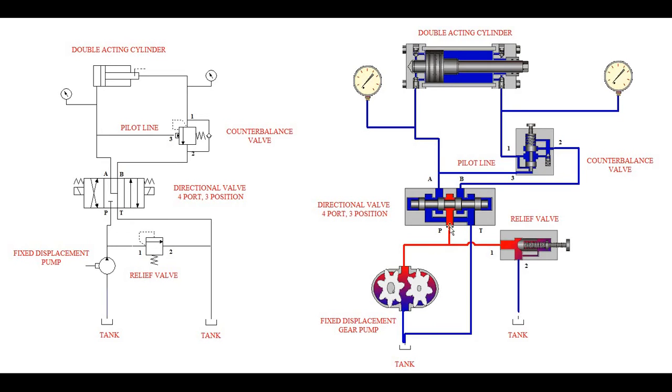P, the pressure goes right up and it's blocked. It can't go anywhere because it's blocked by the spool lands. A, as you can see right there, has space over the land where it's going to go around the spool and come back to T. Same with B. B has a space right here because there's no land blocking it. It's going to come right over the spool and go to T.